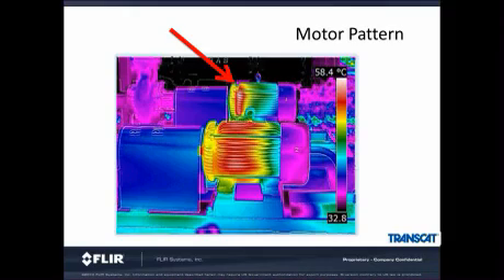And all motors have a thermal rating indicating how hot they can operate. This thermal rating is generally notated on the nameplate of the motor, and that corresponds to a temperature that inside the motor it can operate safely. However, if the outside temperature of that motor exceeds the thermal rating by 18 degrees, meaning that the inside is actually much hotter than the thermal rating it was designed to be, you can expect to cut the life cycle of that motor in half. If you exceed the thermal rating by 36 degrees on the outside, you have now cut the life cycle of that motor to a quarter of its expectation.